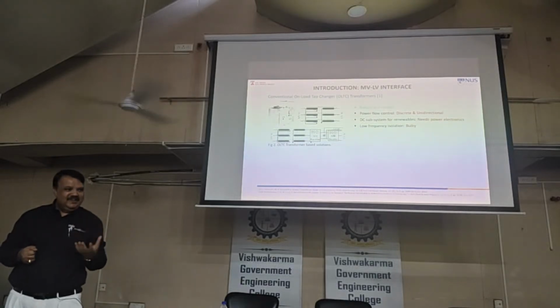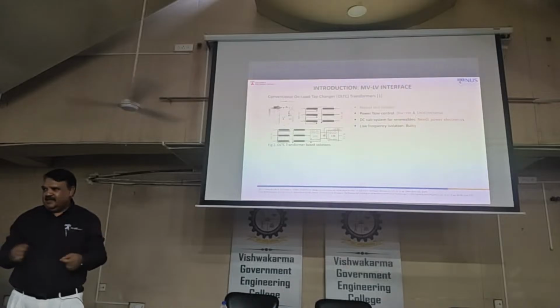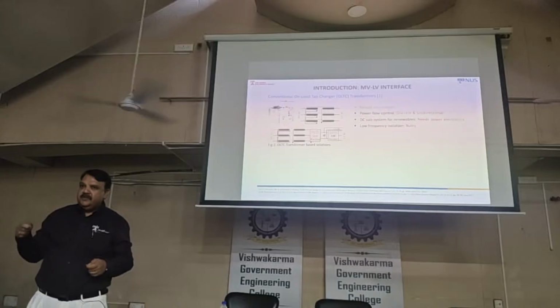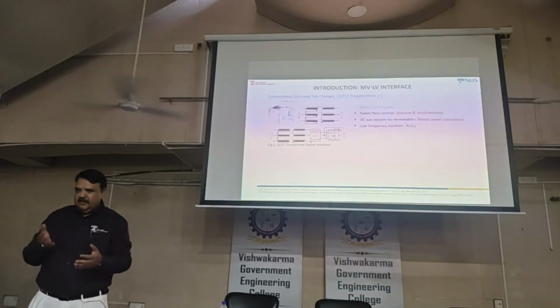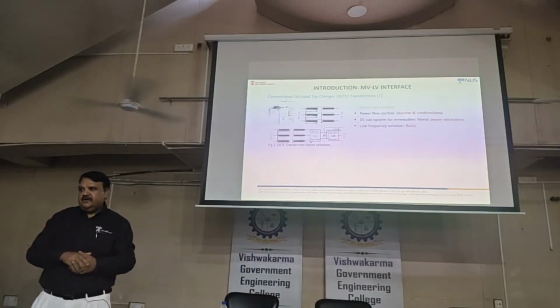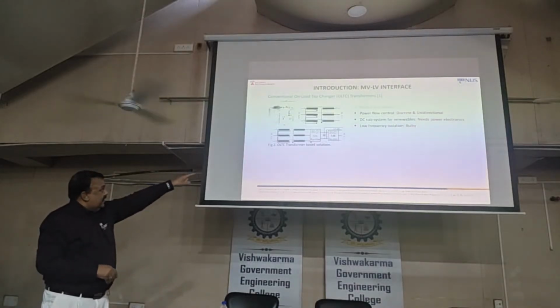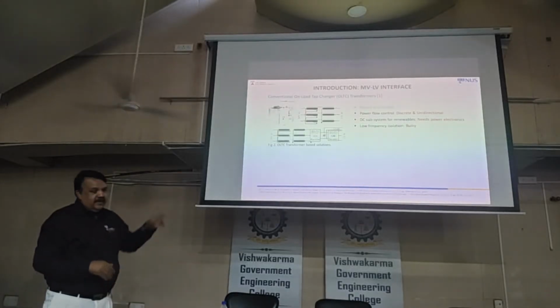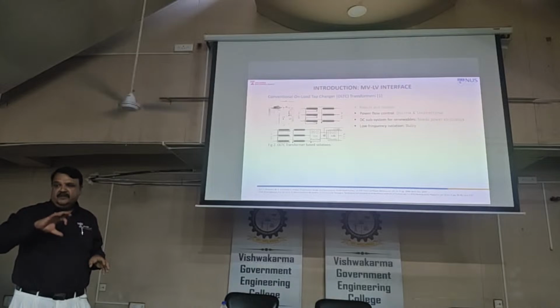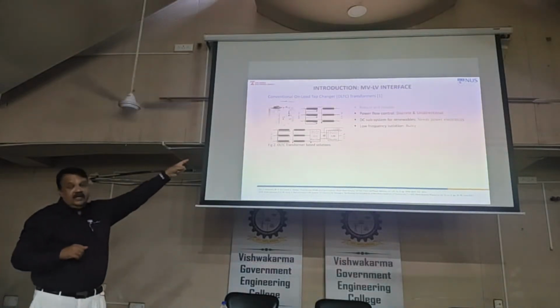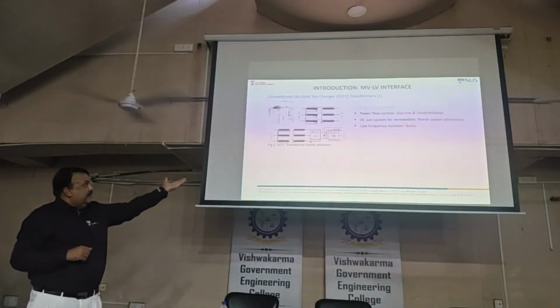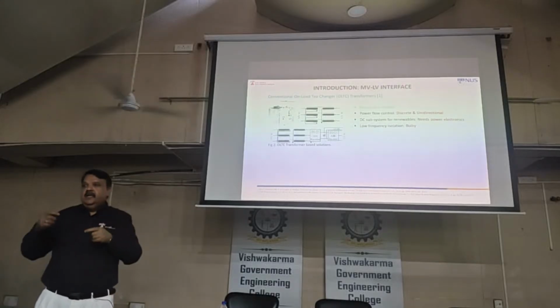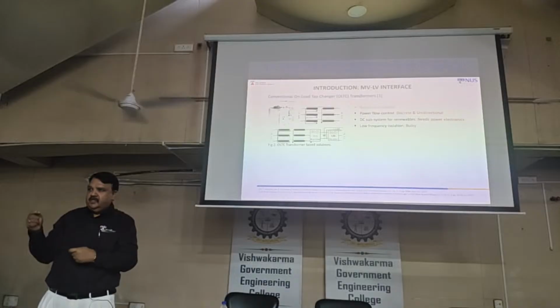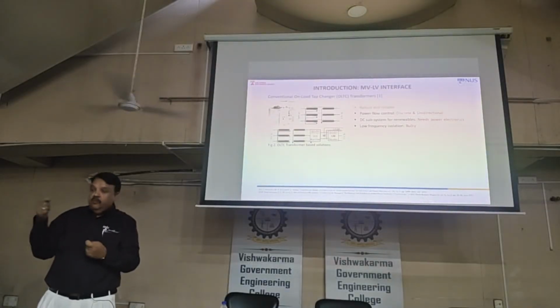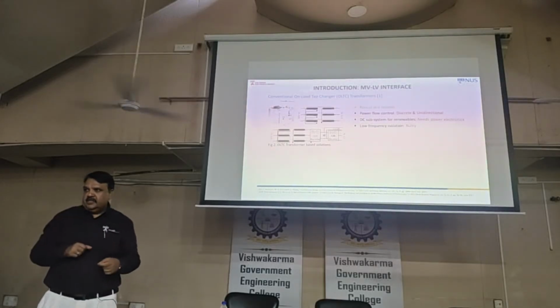The other problem is, if I want to interface DC, like a PV system, how am I going to interface DC with a normal transformer? Cannot do it. Unless you use an AFE rectifier - active front end rectifier - that converts AC to DC. Then I have a DC link that goes to the LVDC. And if I need AC, I go through the inverter to produce LVAC. Once I have a DC link, I can interface the battery storage system, the PV, or wind renewable energy. So I can do all these things, but with additional components.